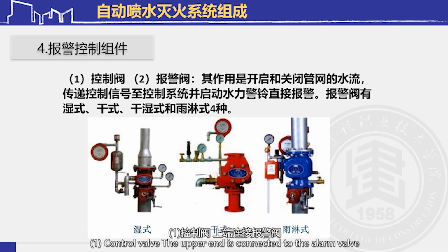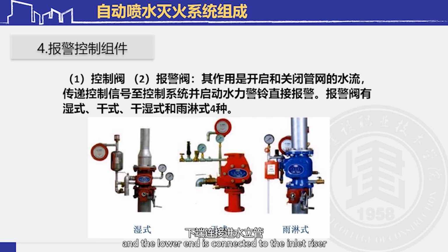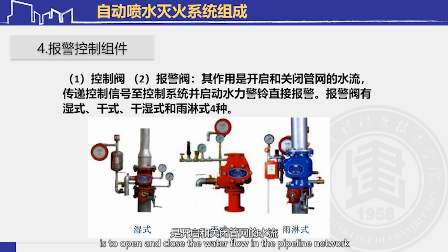Control valve. The upper end is connected to the alarm valve, and the lower end is connected to the inlet riser. Its function is to shut off the water source when repairing the pipeline network and replacing the nozzle after extinguishing the fire. 2. The function of the alarm valve is to open and close the water flow in the pipeline network, transmit control signals to the control system, and activate the hydraulic alarm bell to directly alarm.